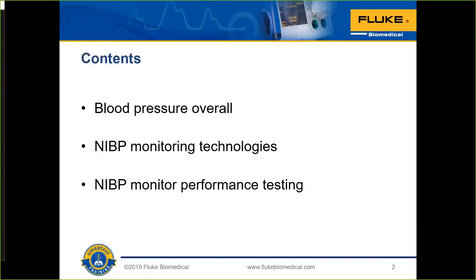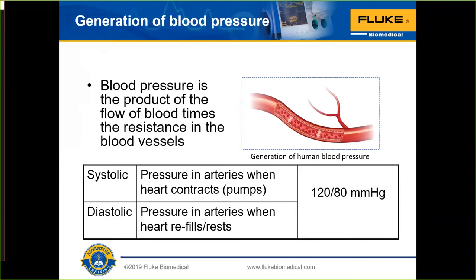Blood pressure overall, NIBP monitoring technologies, and NIBP performance testing. Blood pressure is the product of the flow of blood times the resistance in the blood vessels, and that resistance varies. Your blood vessels aren't just pipes — they flex, constrict, and expand. When we make this measurement, we're looking for two different parts: systolic, which is the pressure in the arteries when the heart contracts, and diastolic pressure, which is the pressure in the artery when the heart is relaxed.